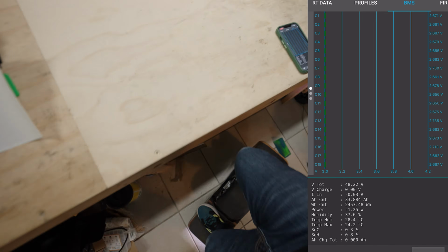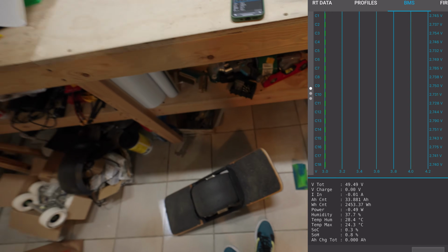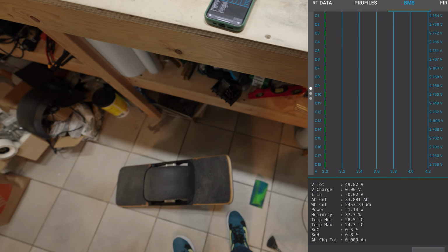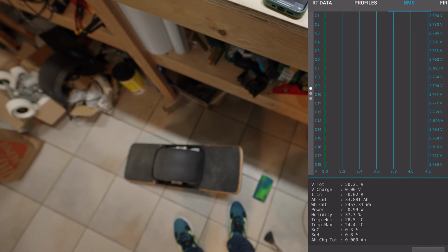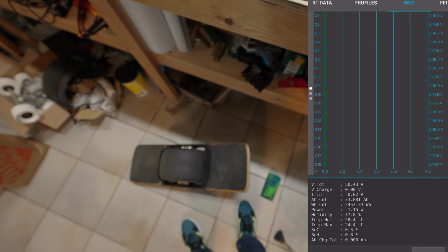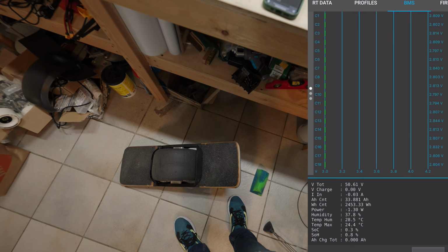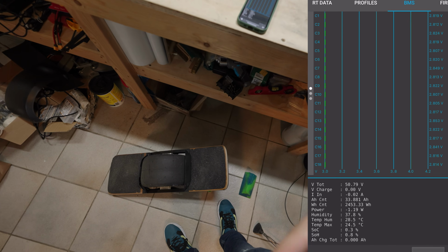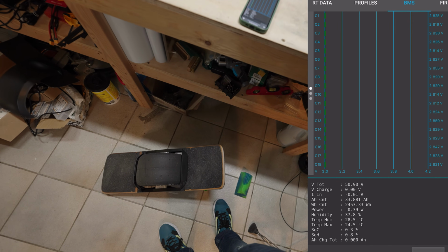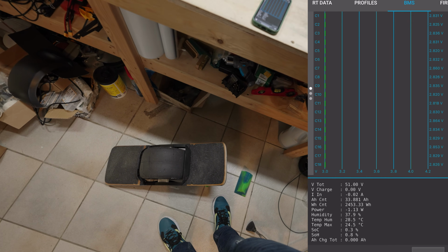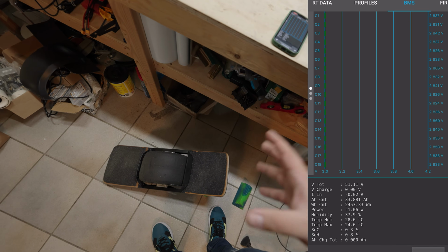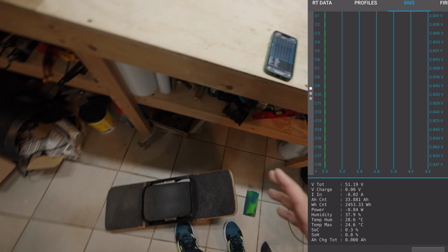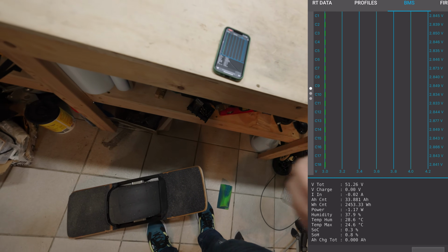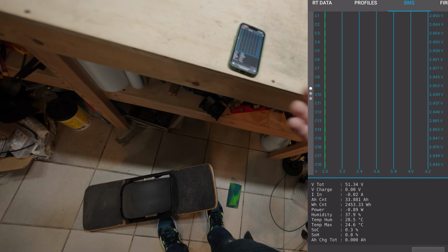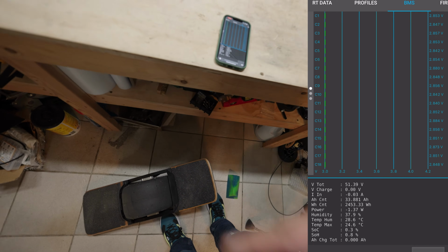The reason you see a massive spread down at the bottom is because the variances in capacity per cell, per parallel group, are most magnified at the bottom, where you simply don't have a lot of energy left. That's just a characteristic of electrochemical energy stored in cells: when you've depleted them, there's not enough left and the variances reveal themselves. That's natural.